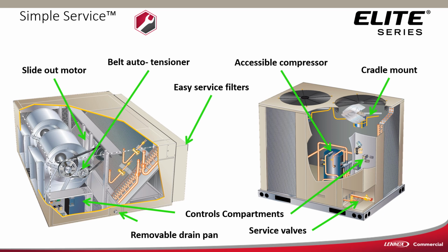Looking to the right at the condenser, you see the accessible compressor. It's easy to get to. In this case, it's a single 2-stage compressor. If it was a larger unit, it could be 2 compressors there. Service valves, these are back-seatable king type service valves, so you can close these and put this unit into a pump down. And the cradle mount condenser fan mounts, same as our package units. We do not take a condenser fan motor, flip it upside down and bolt it to the basket. Over time, the weight of that motor is going to pull that basket down, and when that fan blade drops below that shroud level around the blade, all bets are off on the performance of the system. In fact, if you put an amp meter on there, you'll see a huge difference in the amp draw.